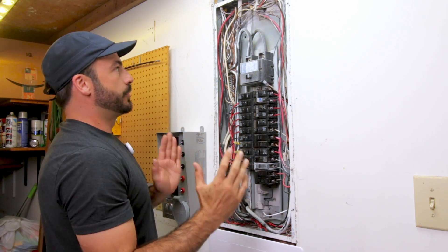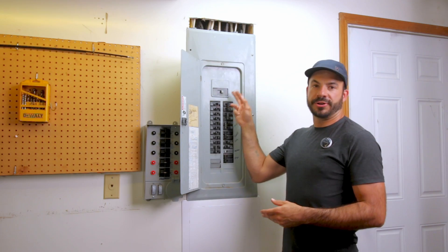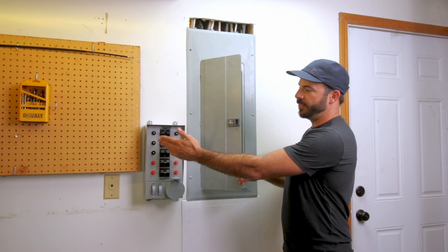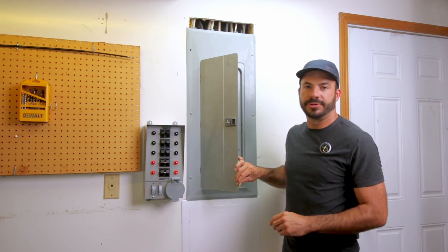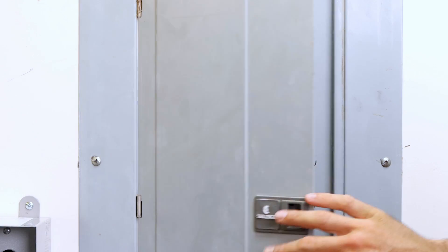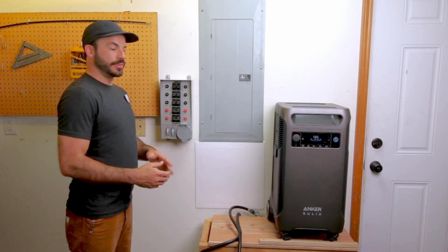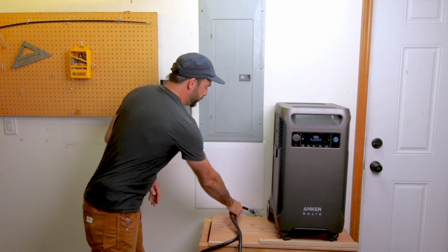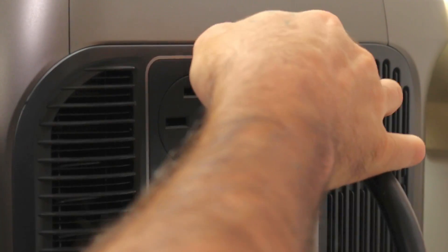Now that everything's wired up, we reinstall the cover on the circuit breaker panel and start testing. We flip the main breaker on, reset all breakers to their normal operating position, then head over to the transfer switch, turn them all on, and set them to 'line' to receive power from the grid. To connect loads to the Anker Solix F3800 in a power outage, grab the cord and plug it into the 240 volt receptacle on the Anker Solix, power it on, then connect the other end to the inlet box.